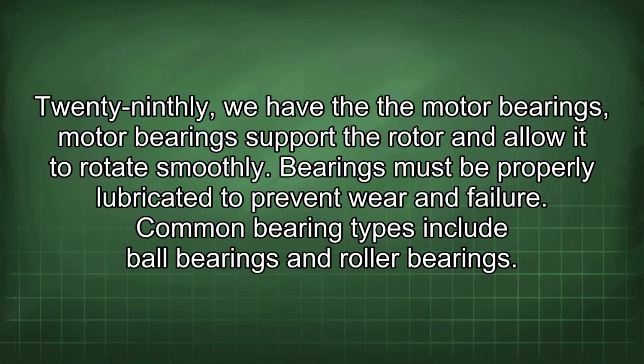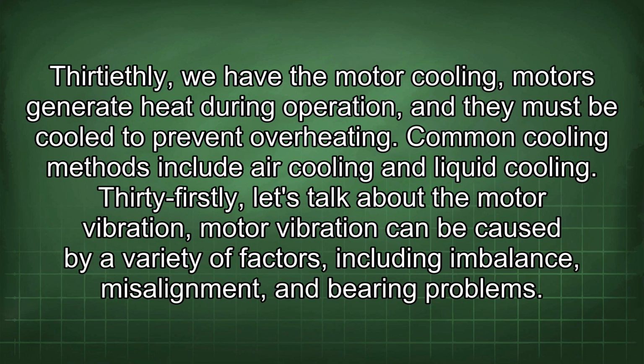Twenty-ninthly, we have the motor bearings. Motor bearings support the rotor and allow it to rotate smoothly. Bearings must be properly lubricated to prevent wear and failure. Common bearing types include ball bearings and roller bearings. Thirtiethly, we have the motor cooling. Motors generate heat during operation, and they must be cooled to prevent overheating. Common cooling methods include air cooling and liquid cooling.